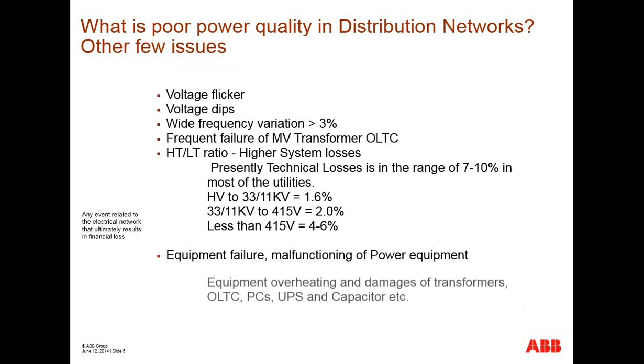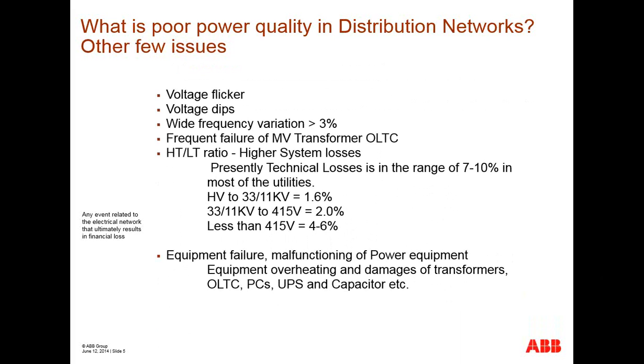Equipment failure and maloperation are also among the reasons of poor power quality, with equipment overheating and damage of transformers, OLTC, PCs or UPS. And with more electronics being introduced into this distribution network, such as digital relays, those things are also getting affected because of the power quality issues.